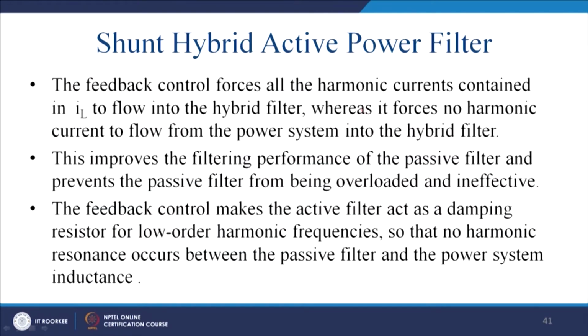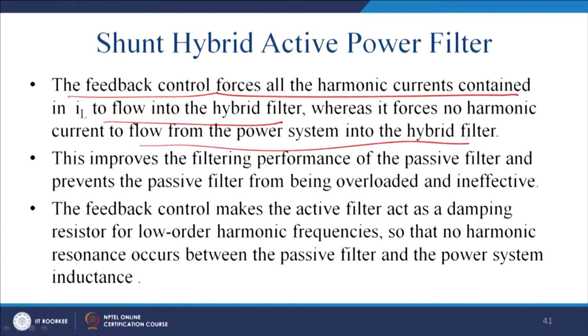Thus we can say that the feedback control forces all the harmonic current content in IL, that is the load current, to flow through the hybrid filter, whereas it forces no harmonic current to flow from the power system into the hybrid filter. This improves the filtering performance of the passive filters and prevents the passive filter from being overloaded and ineffective. So, this is the way you have to take into consideration all those aspects of the passive filters.